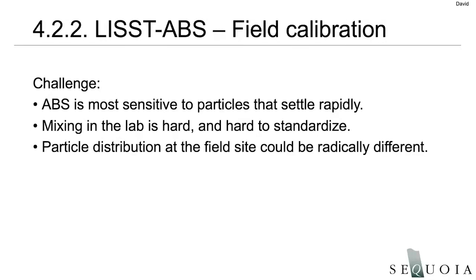We get a lot of questions from users, again, who are accustomed to calibrating their optical or their turbidity sensors. And they want to know how to get the most accurate data with their ABS. The fact is, it's hard. To make a measurement using these larger particles, they do settle quite rapidly. And it took us quite a bit of experimentation to settle on a combination of mixing, the vessel geometry, how rapidly we mix, and so on. It took a lot of trial and error to come up with a stable setup that we can use in the lab. I advise most people that it's probably not going to be worth their trouble to duplicate that effort themselves. And I encourage them to actually use in situ data for calibration.